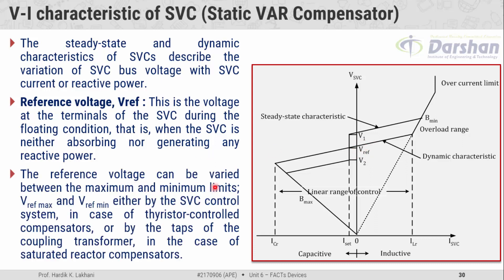The reference voltage can be varied between the maximum limit V1 and the minimum limit V2, also denoted as V_reference_maximum and V_reference_minimum, either by the SVC control system. We can increase or decrease the voltage magnitude from V_reference to V1 or V2 using the control system. If the SVC is made up of thyristor control compensator, we can control this by controlling the firing angle, or by the taps of the coupling transformer in the case of saturated reactor compensator.